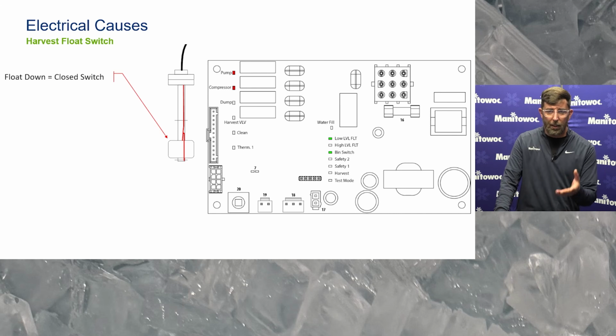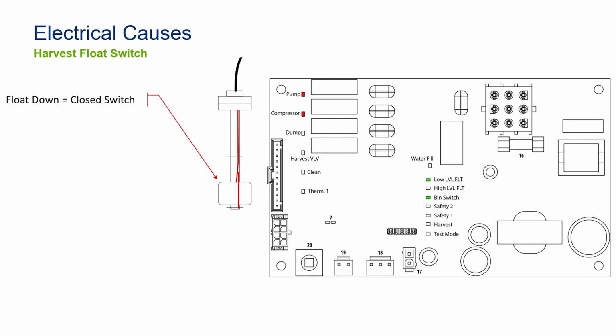So here we are. This is the control board right now. The float is down, and this is going to be the harvest float switch. The float is down. As we said before, that creates a closed circuit, and with a closed circuit, the light should be off. The harvest float corresponds to the low-level float light on the control board, that top light in the middle there. It's still lit green and the float is down.